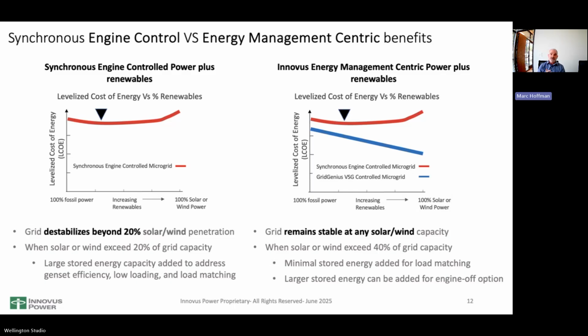So the more solar and wind you put on your synchronous grid, that's essentially the same thing. You don't know it's coming until it's there, and now the engines or genset are trying to react to a load change. At some point above 20% solar and wind, it can't stay within a very narrow range - unlike your car, which can drift from 55 to 65 or 50 to 70 miles an hour, maybe getting a speeding ticket at 75. In a genset, frequency and voltage have to be much more tightly controlled, so now you've got a problem and a risk of an outage.